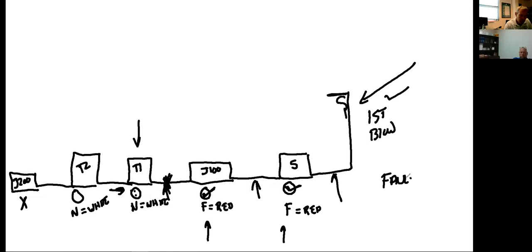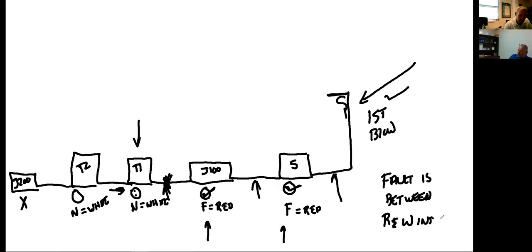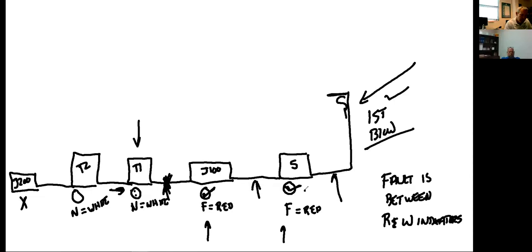The fault is between red and white indicators. That's a simplistic way to put it. If we're using flashing lights, I'd have the fuse blown as the first indicator, this would be flashing, this would be flashing, T1 would not be flashing. So I would know it's between the non-flashing and flashing indicator. Does that make sense to everybody?